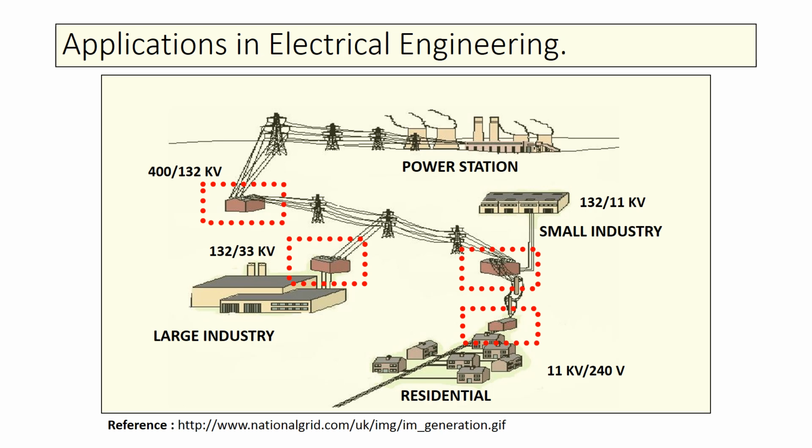One more constraint in generation is that you cannot generate power at larger voltage levels because of insulation constraints. In most cases, the maximum voltage that can be generated is 21 kV. That is also very extreme, but typical voltage ratings are 11 kV, 13 kV and up to 15 kV only. So let us take 11 kV as the generating voltage.